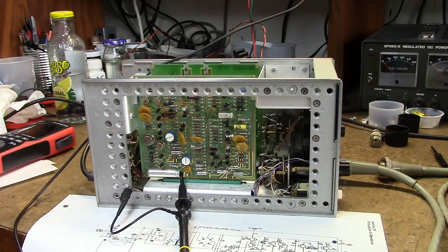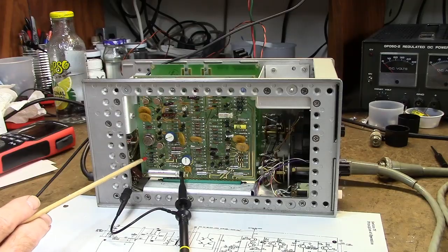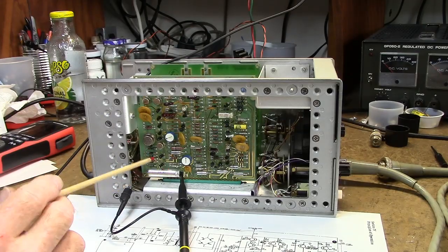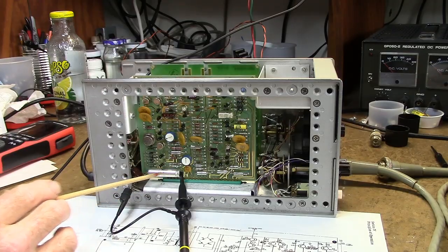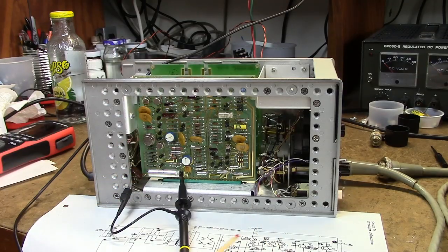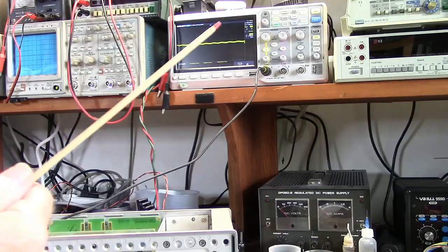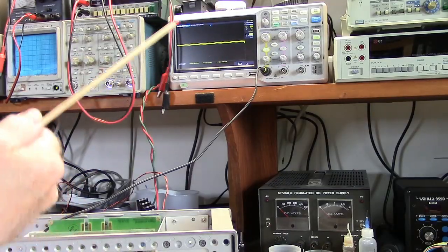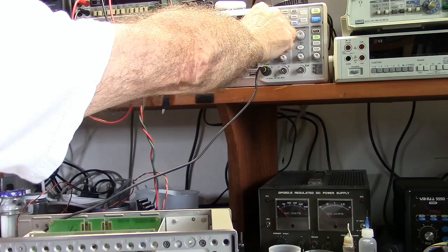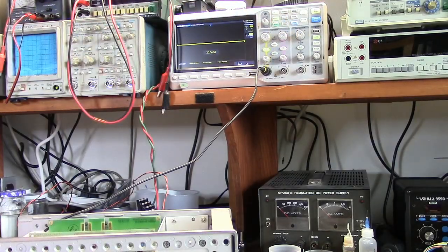I'm also measuring, there's a bridge rectifier here, and then there's a main filter cap here. This is 100 microfarads. So I'm measuring the ripple on the positive end of that cap. Looking at the ripple here on the scope, this is on 5 millivolt scale. It's a pretty clean signal. There's a 20 millivolt scale. The ripple's almost imperceptible, so it looks like the power supply is good. So I'm going to go to the next step, which will be to hook up the bolometer, the thermistor mount, and we'll see if we can calibrate the thing.